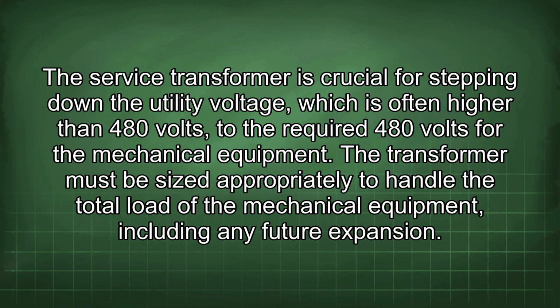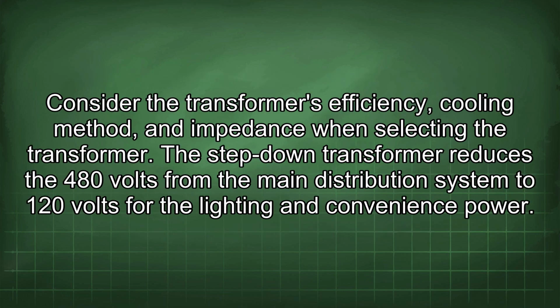The service transformer is crucial for stepping down the utility voltage, which is often higher than 480 volts, to the required 480 volts for the mechanical equipment. The transformer must be sized appropriately to handle the total load of the mechanical equipment, including any future expansion. Consider the transformer's efficiency, cooling method, and impedance when selecting the transformer.